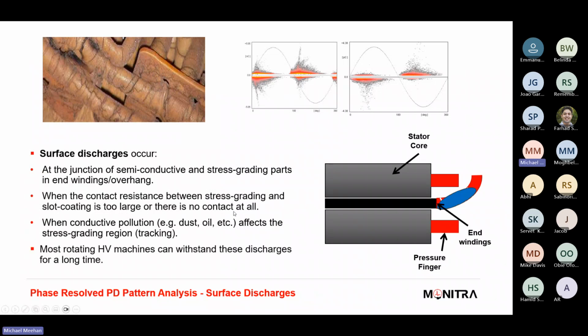So most HV machines can withstand these discharges for a long time. It's a bit like we said earlier, the insulation is designed to be PD tolerant. It's not a PD-free setup based on the way that the machine is configured and just by its design. So it is PD tolerant, but it's tolerant to a point. And obviously we need to monitor that point and make sure it doesn't get beyond it.